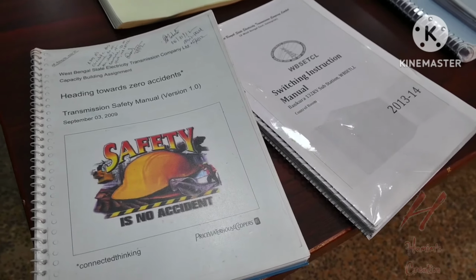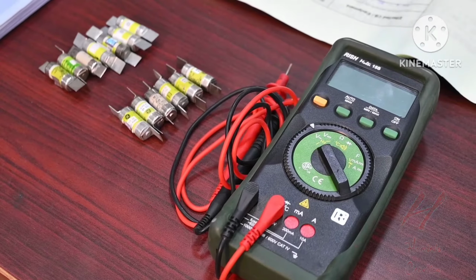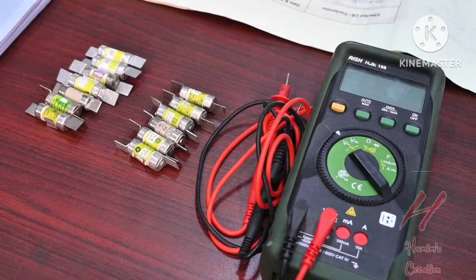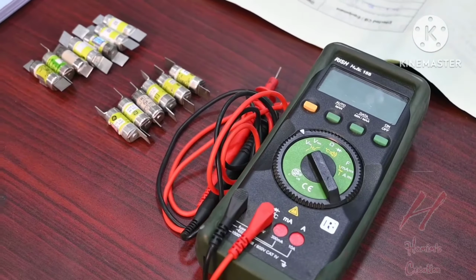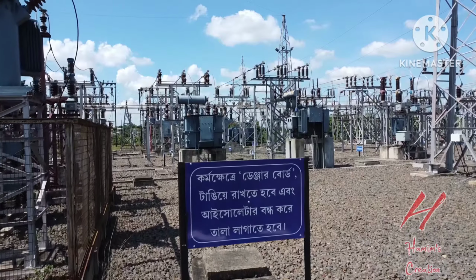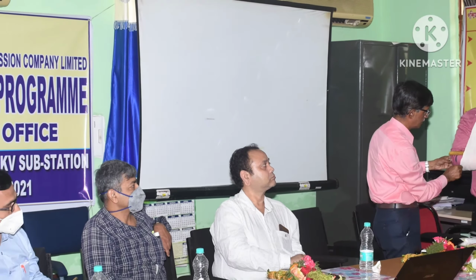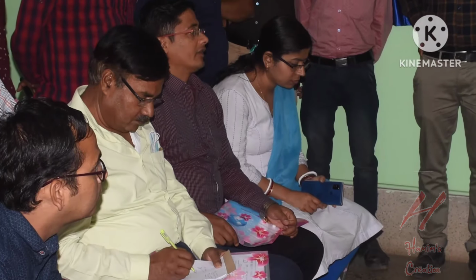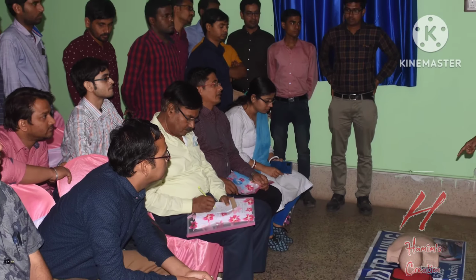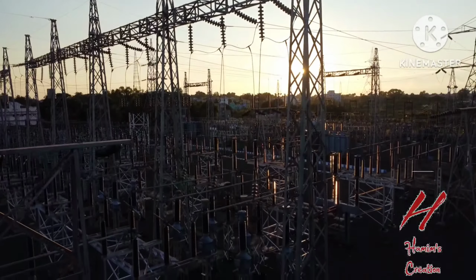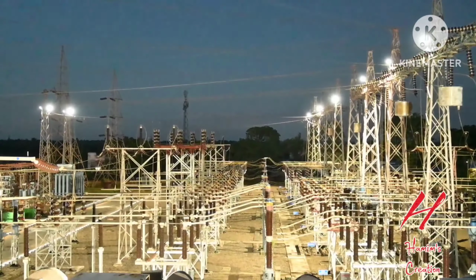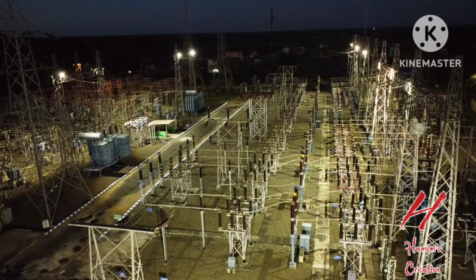Switching instruction, safety manual, drawings, spare fuses with multimeter are always kept ready to use. Bay marking and phase marking are properly done at switchyard. Various safety posters are also placed at both control room building and switchyard area for general safety awareness. Safety awareness program has been arranged last year under Bankura area office for face-to-face training and interaction by distinguished safety personnel. Illumination is bright and clear at Bankura 132 kV substation and maintained regularly.